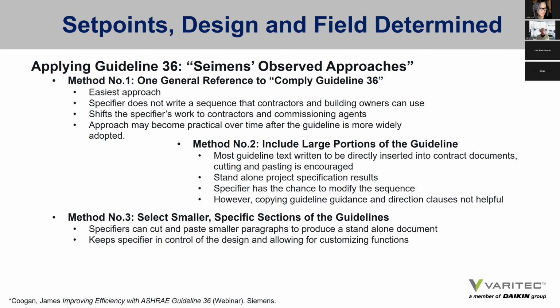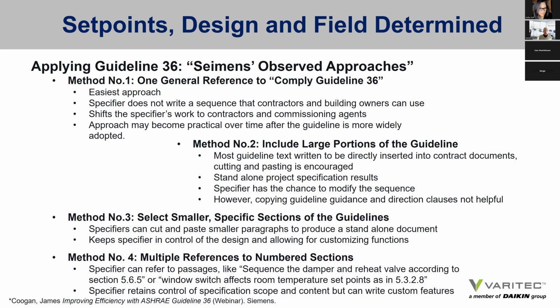Another method is where smaller sections are discretely cut out that address specific sequences for a specific design concept. Again, this can be cut and pasted, but it keeps the specifier in the actual creative sequence writing mode. And consequently, their system will more likely perform directly to the design intent of the guideline and reduce perhaps improper interpretations from the installing contractor or the commissioning agent. And then what we'll probably see more in the future are multiple references to numbered sections that provide the language of how a piece of equipment is to operate under given conditions.